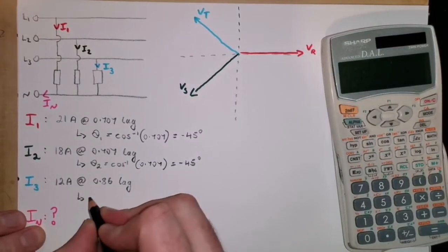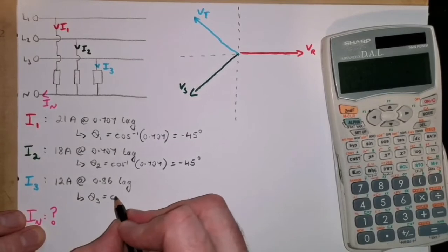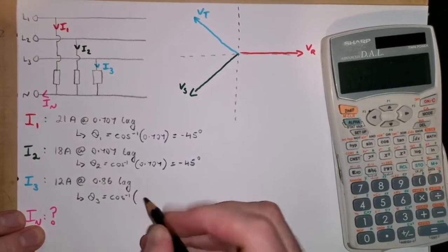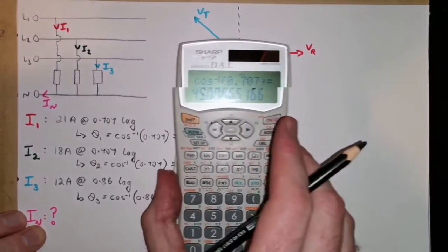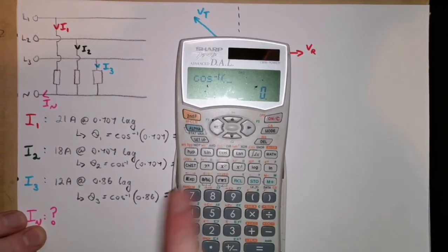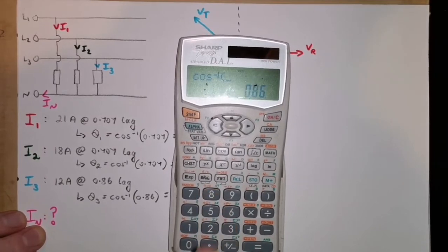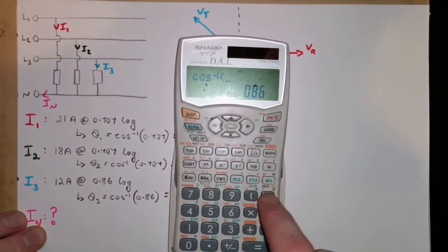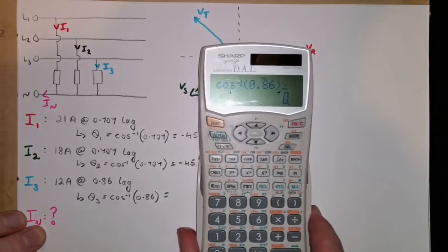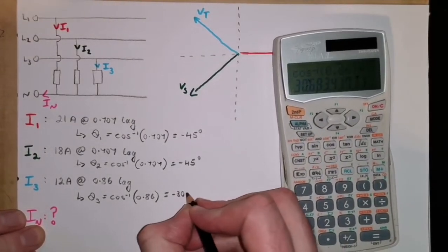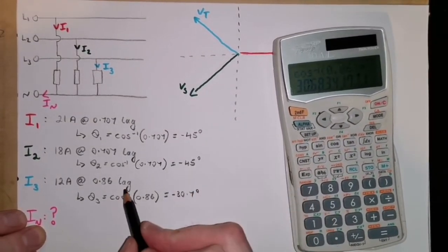And then finally, theta 3, same method, 0.86 is our power factor, and I'll just double-check what the value of that one is. It's the cosine inverse. On my calculator here, it's shift cosine for that, and 0.86. So, this is closer to 1, so our angle should be less than 45. We have 30 point, I'll go with 30.7. And it's minus 30.7 because it's also a lagging power factor.